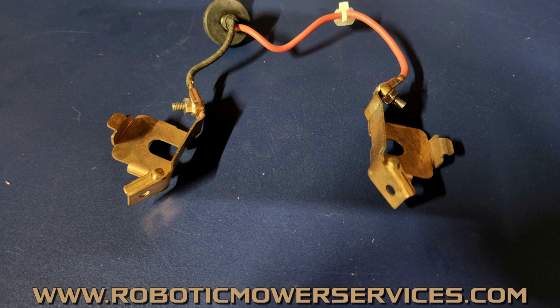You can also check the resistance from one end of your low voltage cable to the other. Check the positive, check the negative, and make sure both have very low resistance. When I say low resistance, you want to be down around 1 ohm, not up at 3, 5, 10, or anything like that.